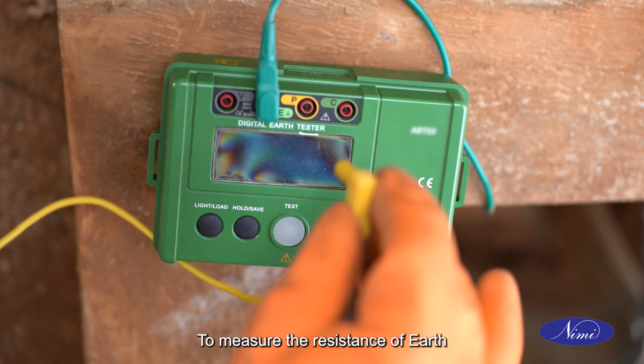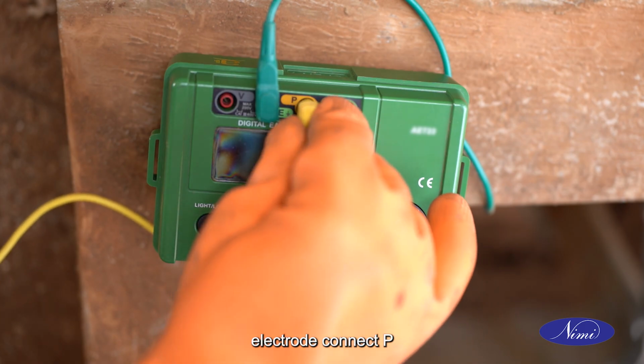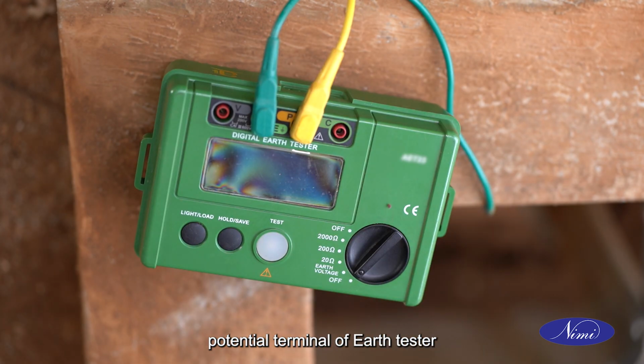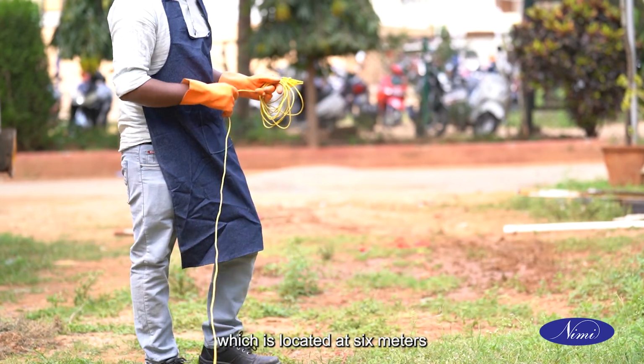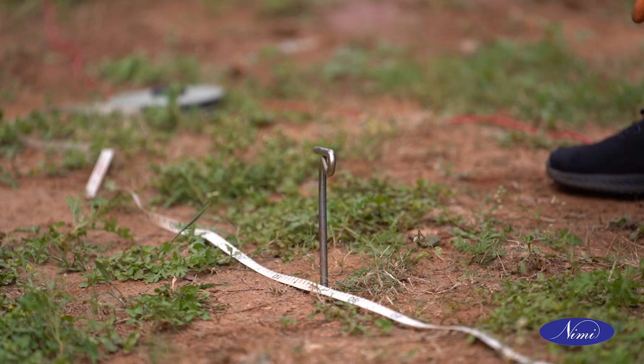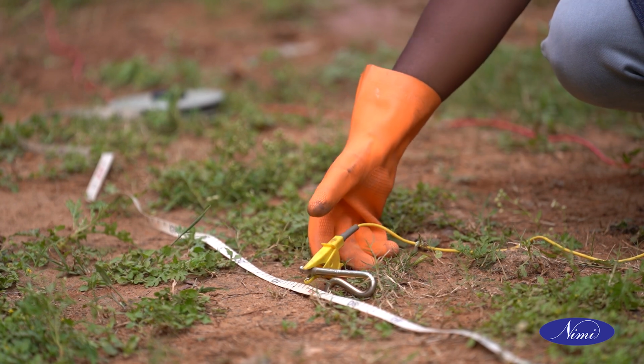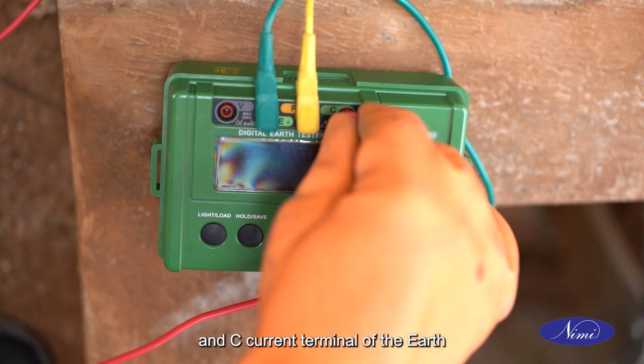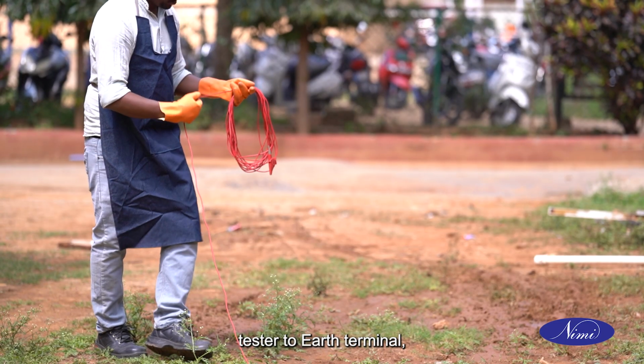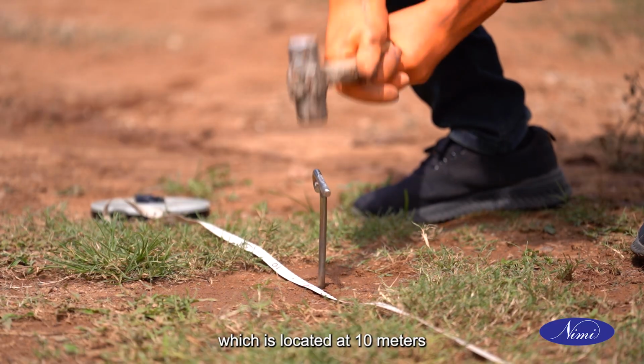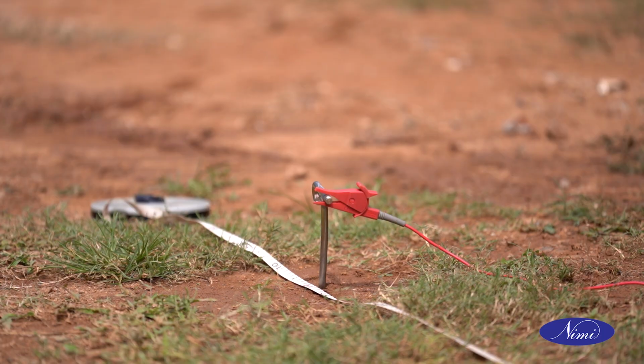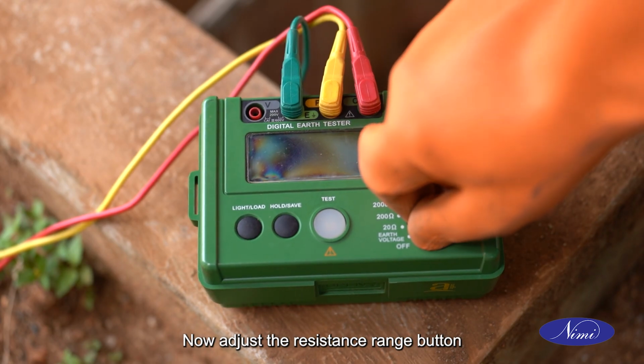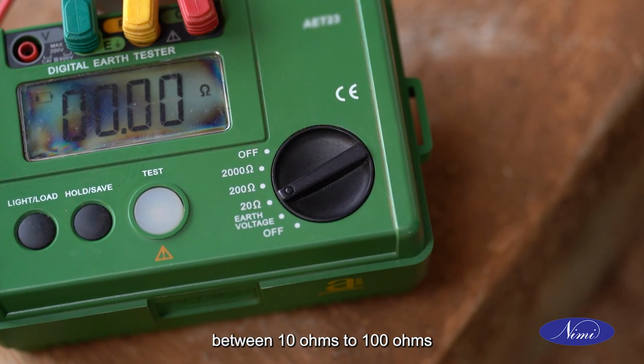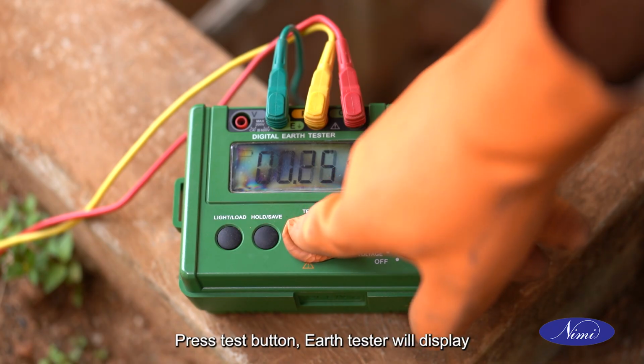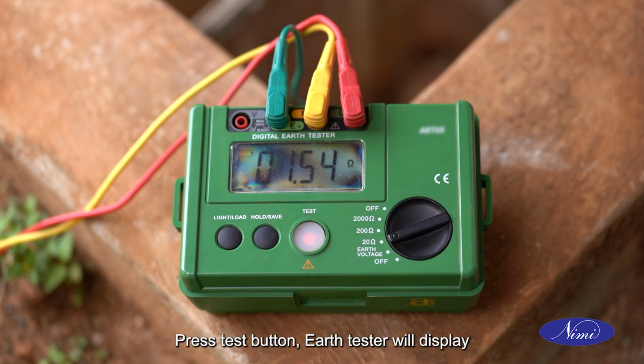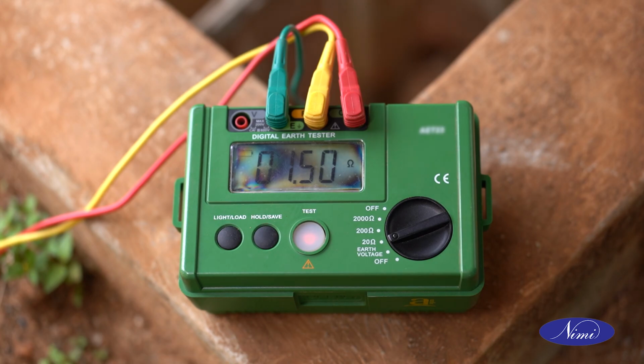To measure the resistance of earth electrode, connect P potential terminal of earth tester to earth terminal, which is located at 6 meters, and C current terminal of the earth tester to a terminal which is located at 10 meters. Now adjust the resistance range button between 10 ohms to 100 ohms. Press test button. Earth tester will display the earth electrode resistance.